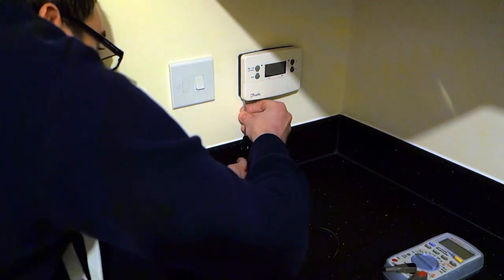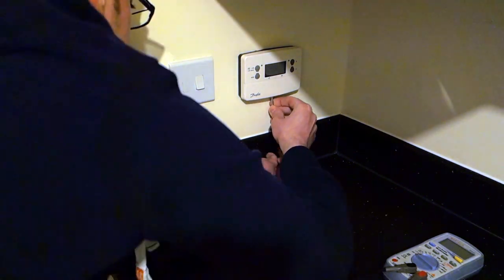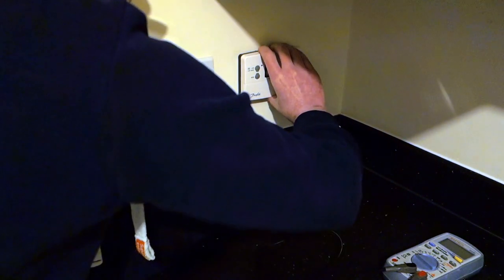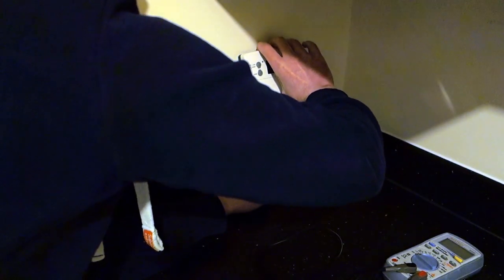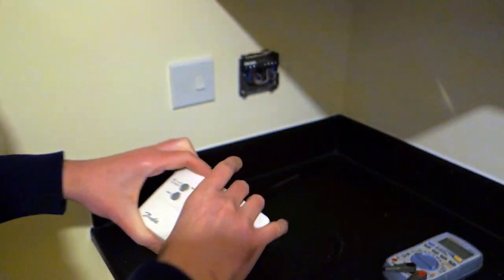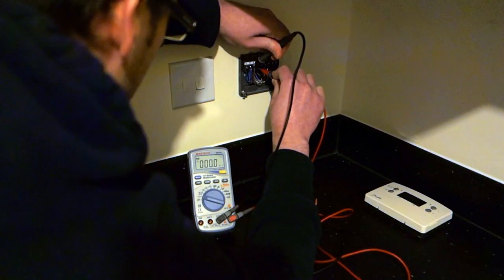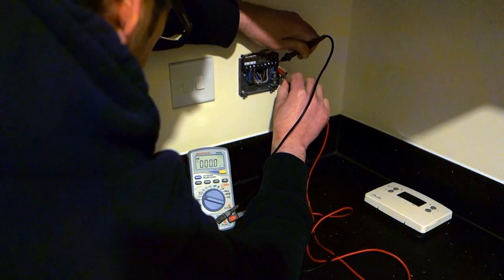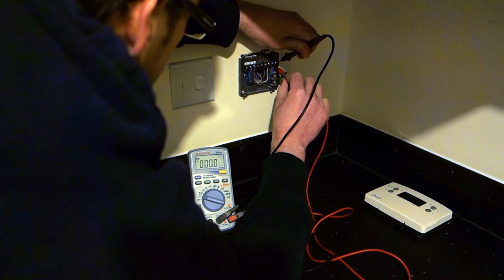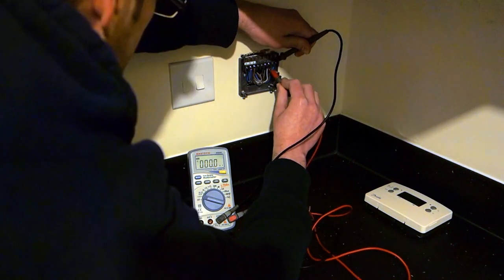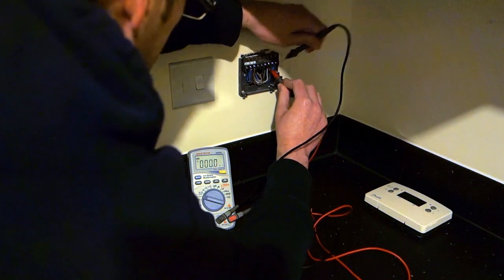you want to unscrew the two screws from the bottom of the programmer and remove it from the wall, and then using a voltage meter or some kind of voltage tester, you just want to make sure that all of the terminals are actually dead and that you've properly isolated the supply.